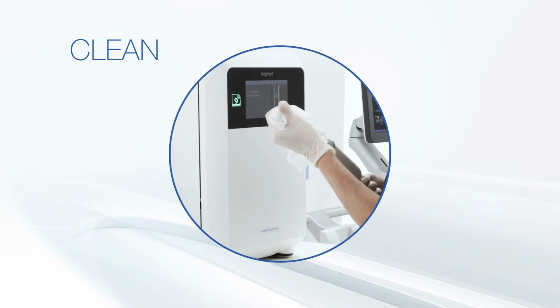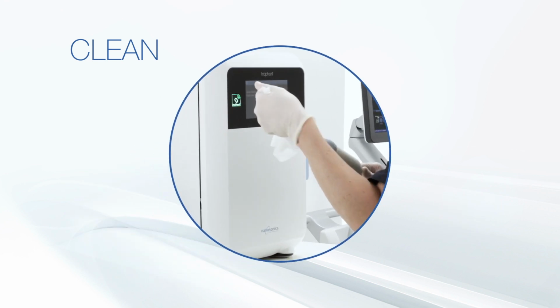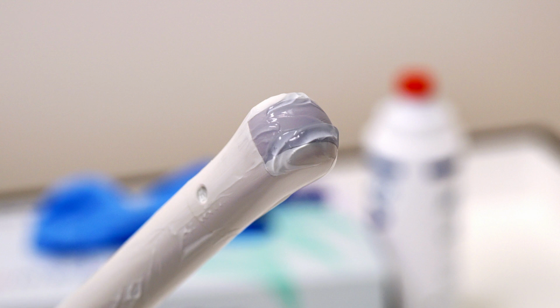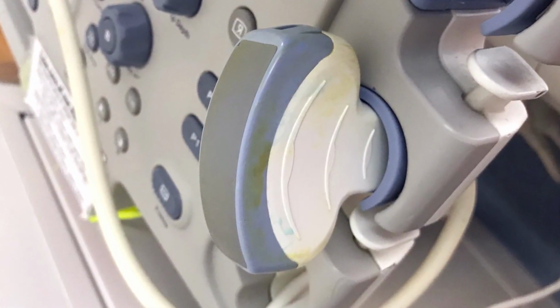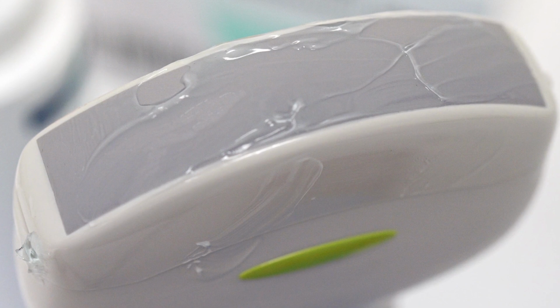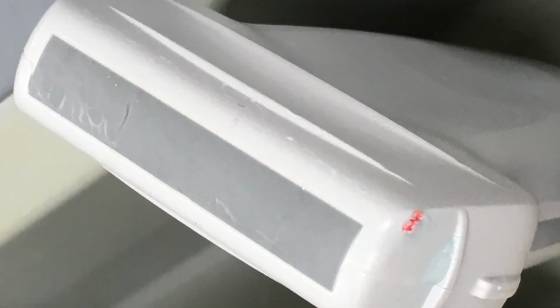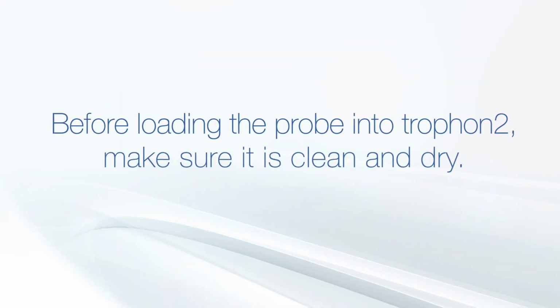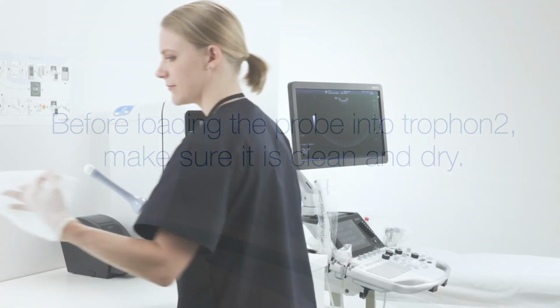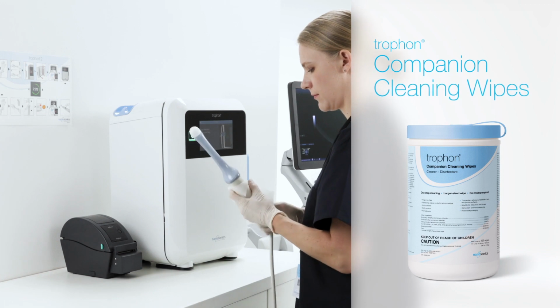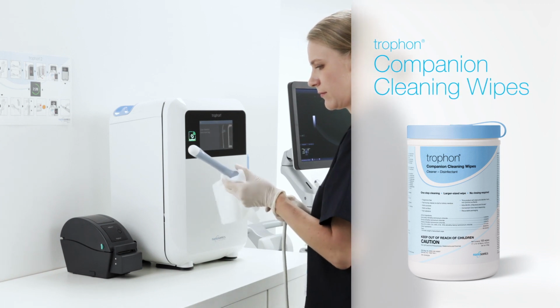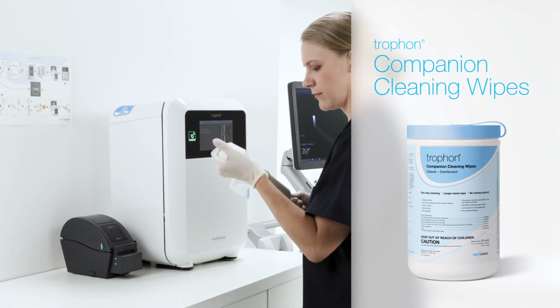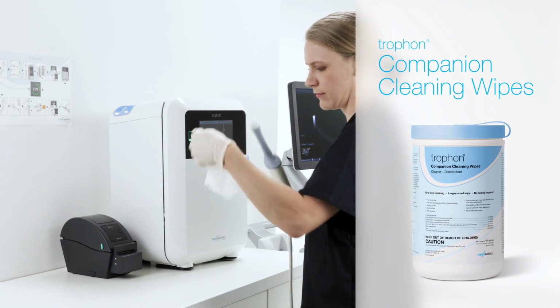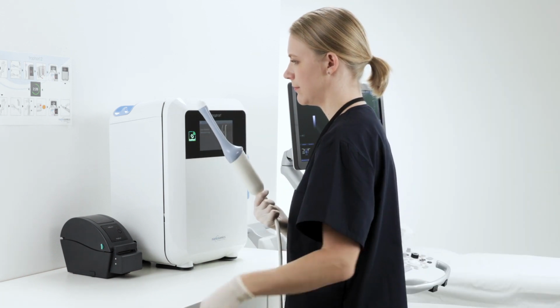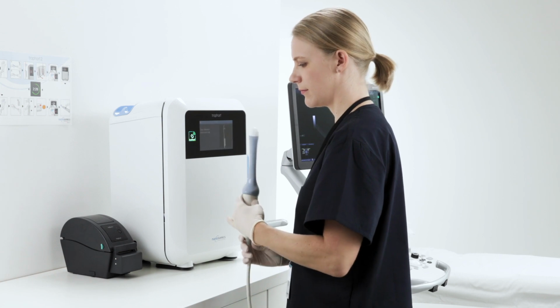Cleaning is the essential first step in reprocessing ultrasound probes. It is key to reducing organic material, microbial load, gel, and other soils on the surface of ultrasound probes. Before loading the probe into trophon2, make sure it is clean and dry. Use a trophon companion cleaning wipe to clean the probe, working your way from the cable strain relief up to the tip of the probe. Visually inspect the probe and repeat the process if needed until it is visibly clean.